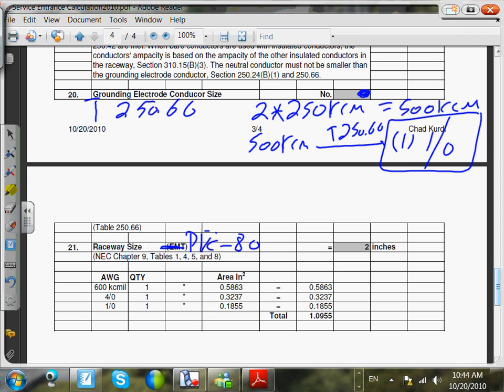And how many conductors are used? 250 here. How many conductors for them? I use 2. So I'm going to change this one. And what was my neutral size? My neutral size was 1 aught. So this one, you don't need this step here. 1 aught for my neutral. And then you're going to find this calculation and you guys are going to size it. You know how to size. All these are different. These values you're going to adjust them.